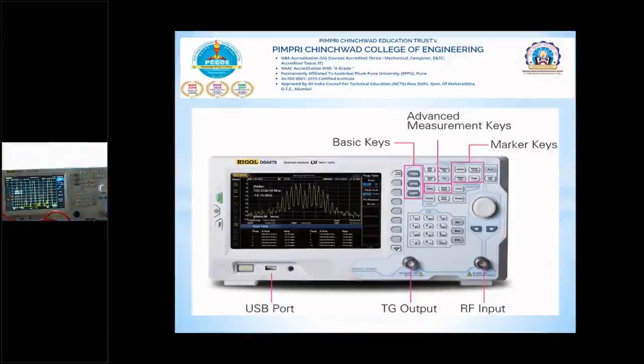As I use the single mode, you can see the spectrum has stopped. It is not in running mode, that is, continuous mode. I have stopped the spectrum here. Now I will use one marker. Another option you can see on the panel is the marker keys. I'm using the basic marker key, that is marker. One marker will appear like this. You can see point 1. Using this knob, if I put the marker at the top of the upper sideband, you can see the frequency here is 1.26199 megahertz. Now I'm moving the knob to the lower sideband, and the marker will appear there. For that purpose you have to use the same knob, this one, turning clockwise or anti-clockwise.